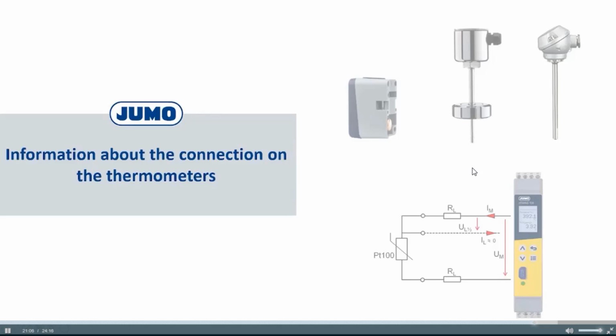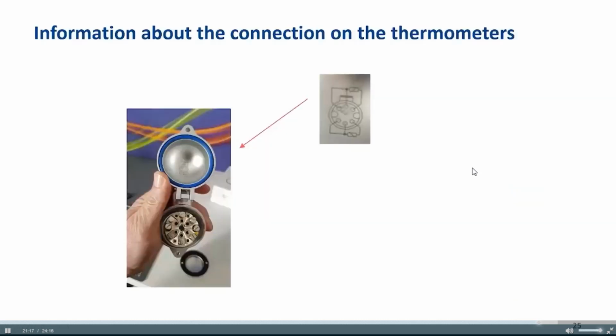Then, how can you find the right connection of your thermometer? Maybe you have 4 pins. What is the one side? What is the other side? In many cases, you find information for the connection on our probes. I hope you can see this. It's not so clear here, but I made a photo of the inside of this head. You see I have here 1, 2, 3, 4, 5, 6 pins. And you see, it's a double RTD temperature probe. This is a cable entry here. And you see how to connect the one RTD and how to connect the other RTD. Many times you have this information on our probes.